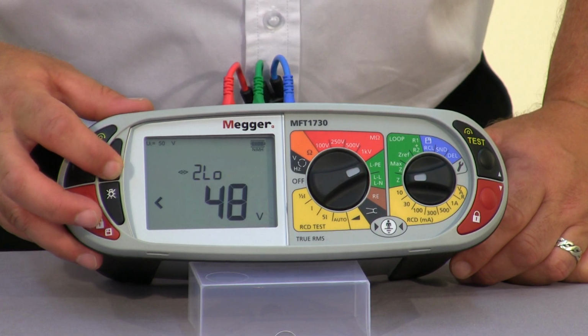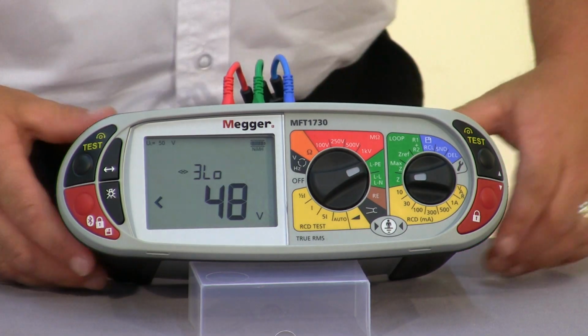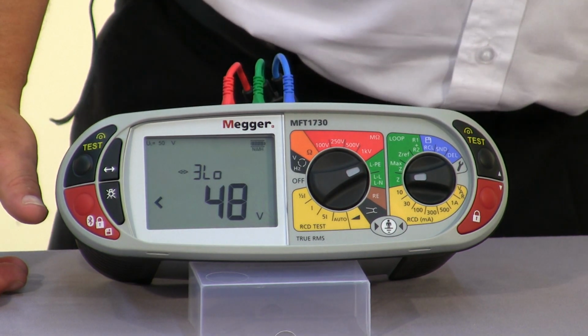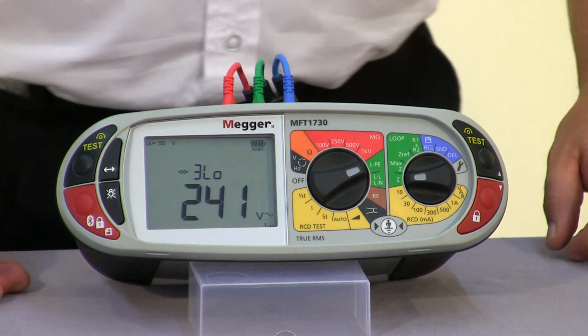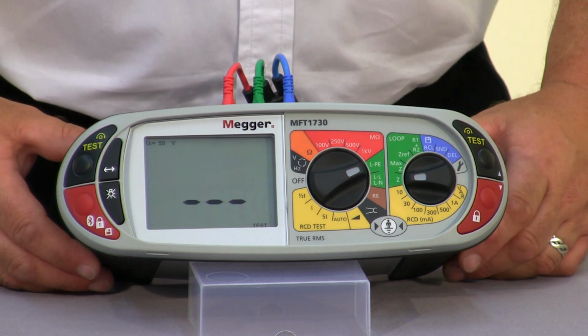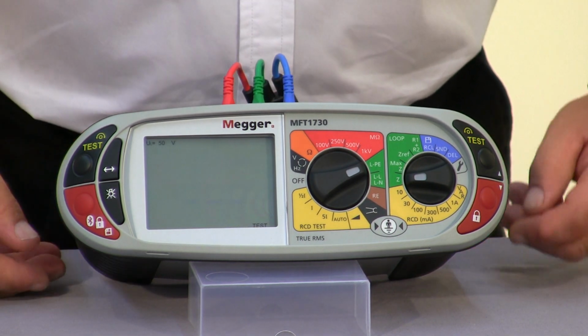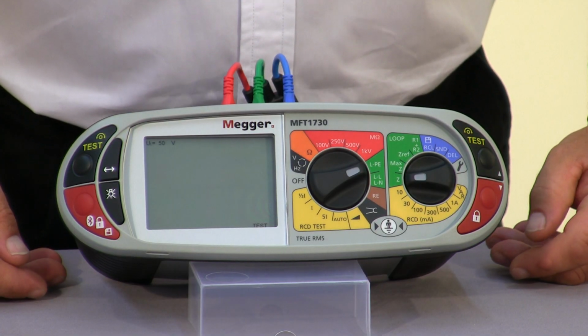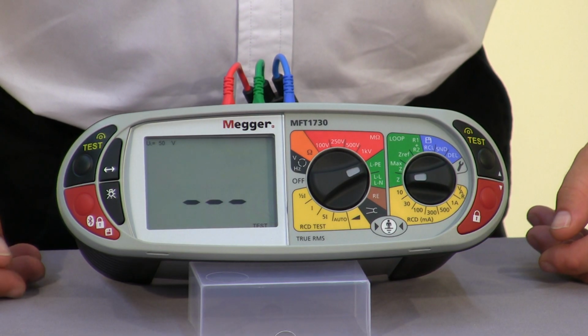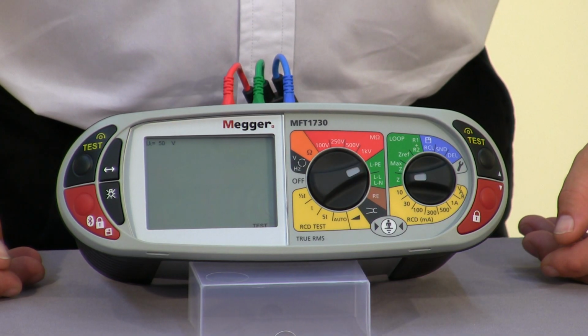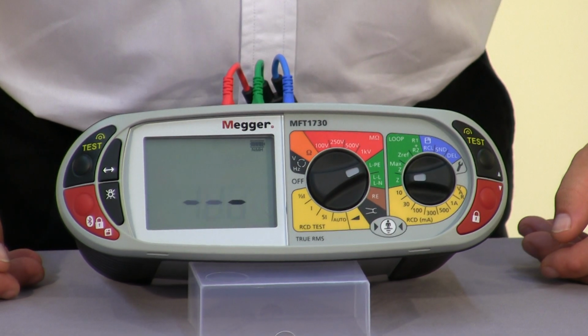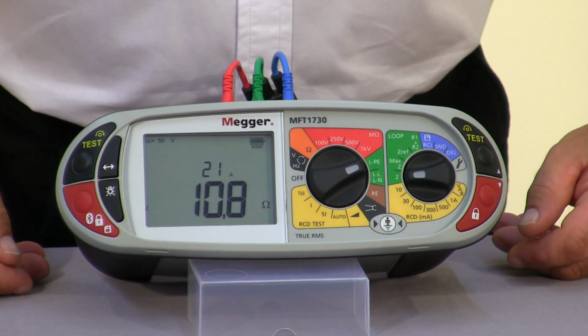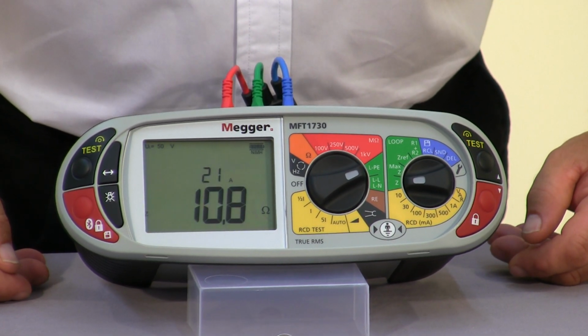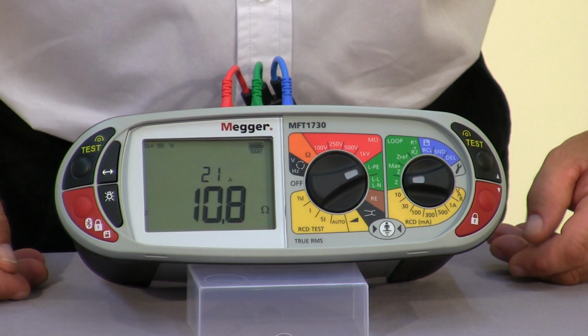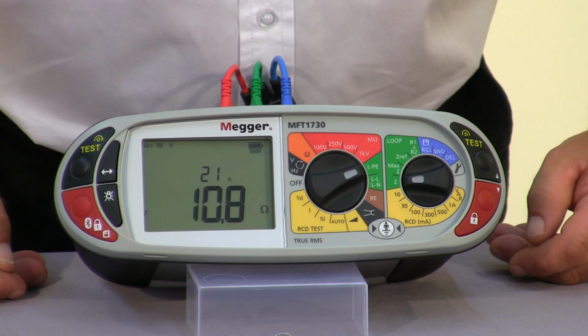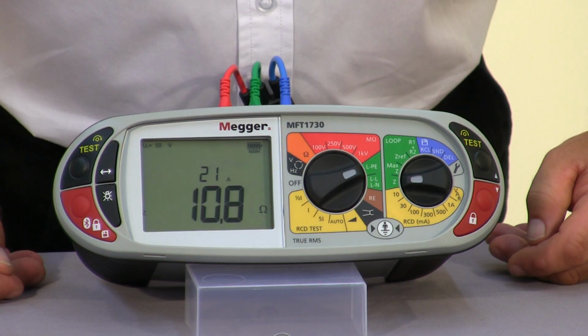So going back to do a standard three-wire test, so live, neutral and earth connections, applying it to the mains voltage, you get an audible indication from the unit which confirms that it's seen the voltage and has started the test. Now you'll notice that I haven't actually nulled out any of the leads. It's not a requirement with the Megger MFT1700 series when you're doing a loop test to carry out any lead null. So the reading we've got here is 10.8 ohms and we have a PFC value of 21 amps.